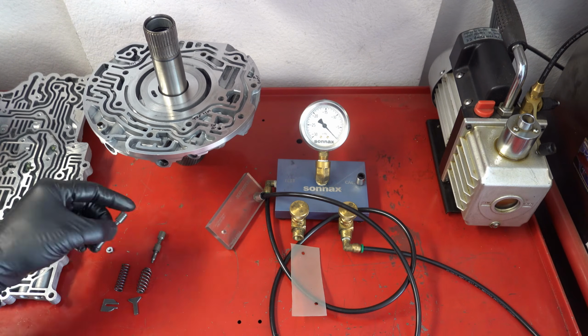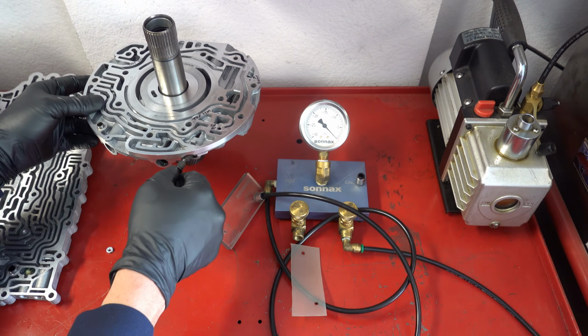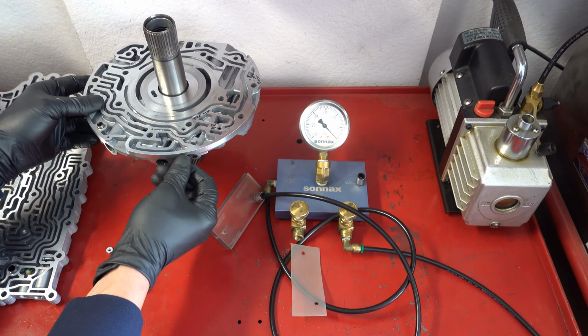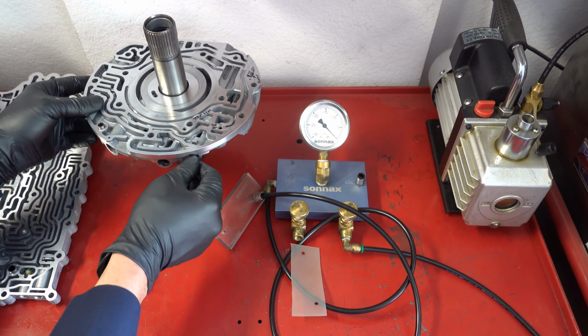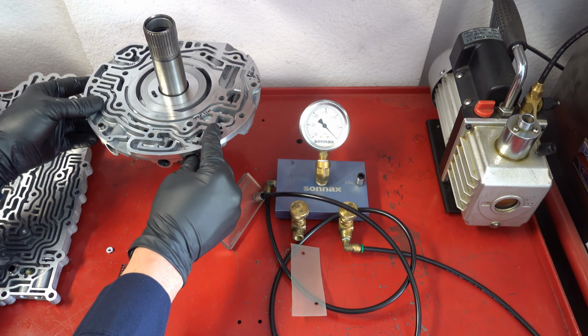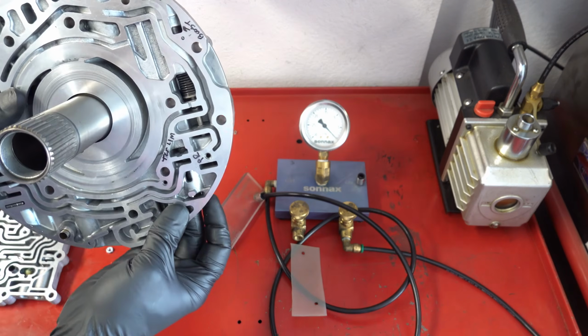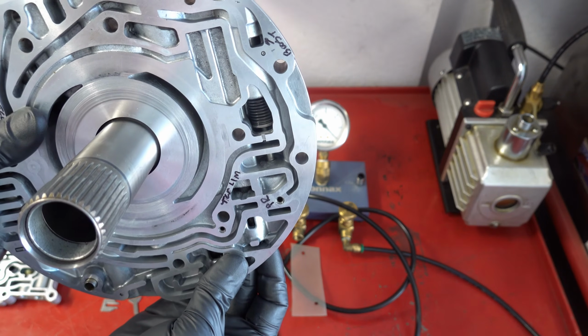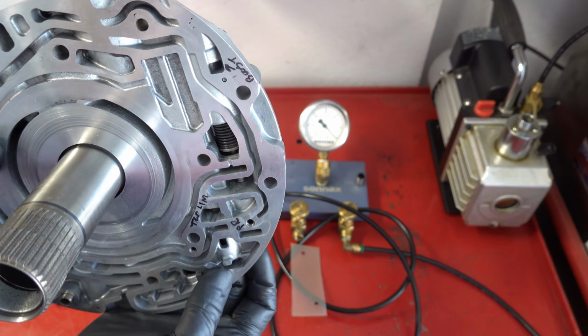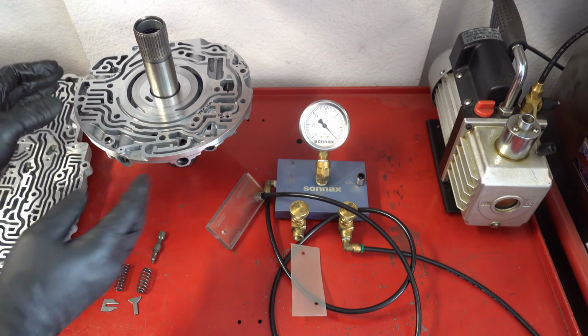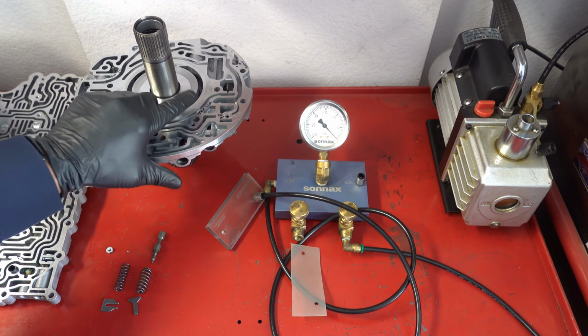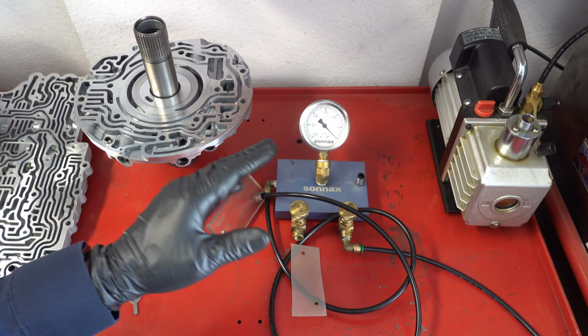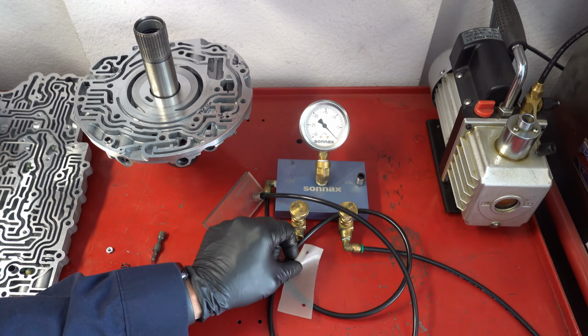What you want to do is insert your actuator feed limit valve, and the valve needs to go in roughly 75% to 80% of the way in. You want to make sure it's fully sealing this circuit. Now, like I said, as soon as I put vacuum to this, we're going to get a reading for about a split second, then it's going to drop to 0.